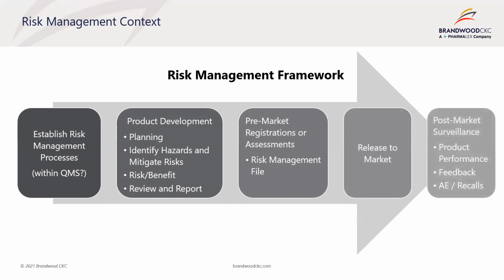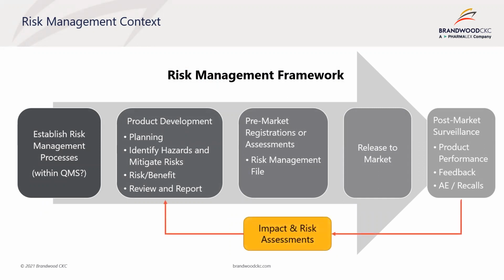During the post-market surveillance phase, feedback from the field, such as complaints, issues, adverse events, recalls, etc., are assessed for the impact to risk. An impact and risk assessment should be performed for all post-market events to determine if any new risks are identified and whether any mitigations are required, which then would require feeding back into product development.